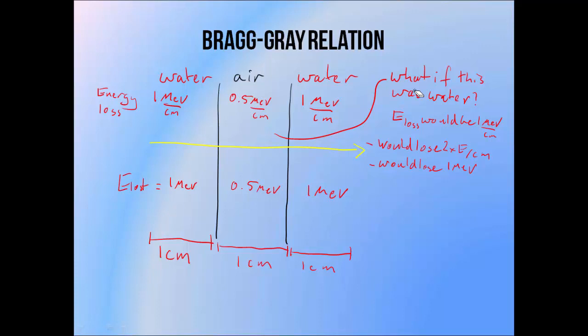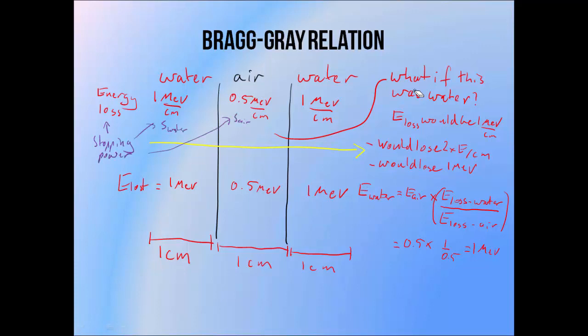Writing it out mathematically, if we replace the air in the middle region with water, the energy lost inside the middle region will be equal to the energy lost if it was still air, multiplied by the rate of energy lost per centimetre in water, divided by the rate of energy loss in air per centimetre. In this case that's the 0.5 MeV lost by the electron in the air, multiplied by the rate of energy loss in water (1 MeV per centimetre), divided by the rate of energy loss in air per centimetre (0.5 MeV per centimetre). This gives the result of 1 MeV. The name that we normally give to the rate of energy loss is the electron's stopping power. So writing the Bragg-Gray equation in a form closer to what you'd see in a textbook, the energy that would be deposited in water is equal to the amount of energy deposited in air, multiplied by the ratio of stopping powers for water and air.